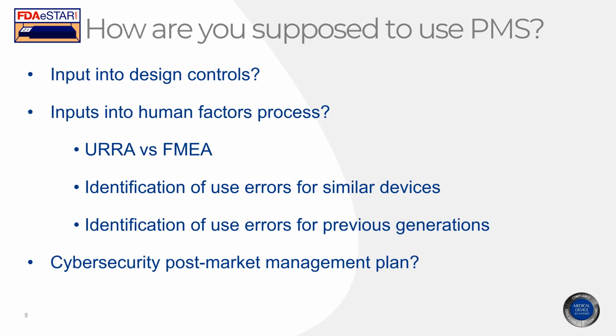So how are you supposed to use post-market surveillance according to the FDA? It's not that you're not supposed to do it. You're supposed to use post-market surveillance as an input into your design process. So when you get feedback about a design, oh, I need to improve this. Oh, it has adverse events. Oh, it has use errors. It doesn't last as long. It requires service. Whatever it is, all that feedback that you get that's post-market feedback for a product that's on the market, that's supposed to be an input into your design control process, and you should be deciding what new products or product revisions you should be making based upon that post-market surveillance. So that's a very specific use of that post-market surveillance data.